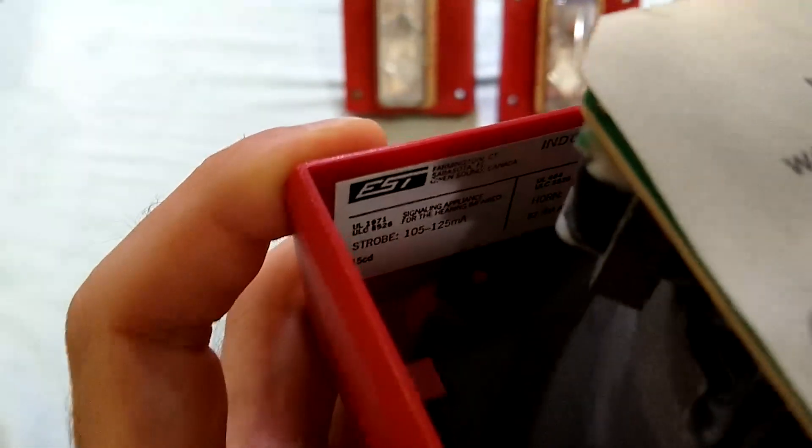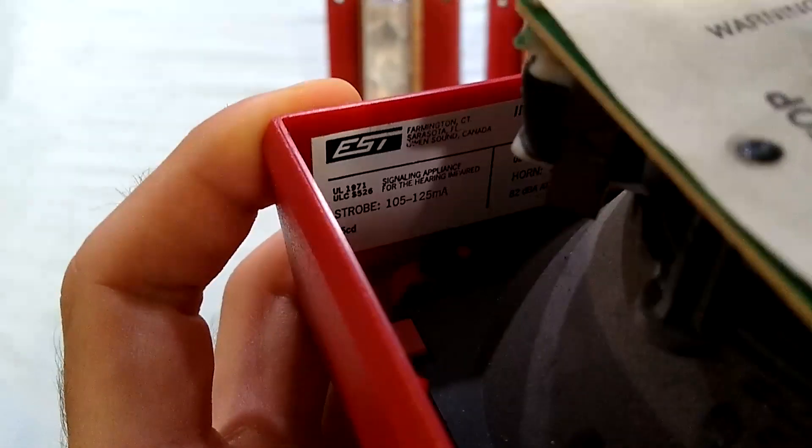The strobe on these, if we look at the tag, is 15-75 candela. So here it has the 15 candela rating. It says signaling for the hearing impaired. And this is the 75 candela rating.